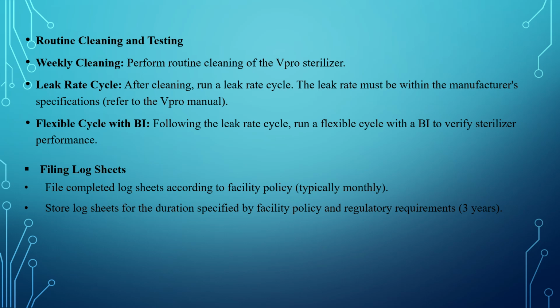Routine cleaning and testing. Weekly cleaning is the routine cleaning of how we clean the machines. After the cleaning, we make sure we run the leak rate cycles. The leak rate cycle is done according to the VPRO specification. As soon as the leak rate test has finished, we run a flexible cycle with BI, to verify its sterilization performance, and then fill in the log sheets.